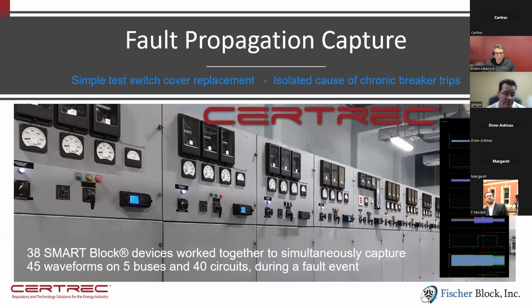And the same device, we call it a smart block, that we just saw there on the solar farm, also has applicability across the grid. This happens to be a distribution substation. This particular implementation, we used a variant of our device that actually becomes a retrofit cover to a Flexi style test switch. And for those on the call today that are familiar with substation architectures, nearly every control panel on the grid, even in industrial plants and on wind farms and solar farms in the local substation, have banks of test switches that you can see underneath our devices there.